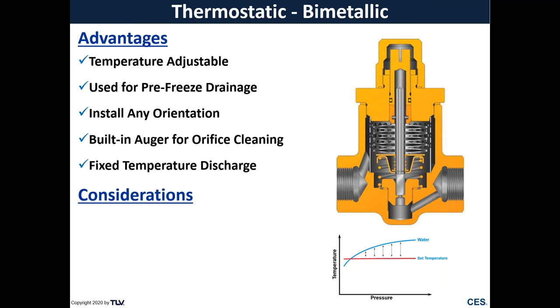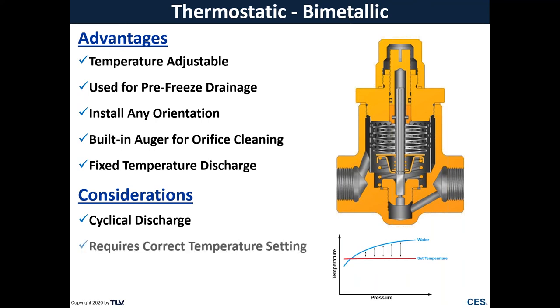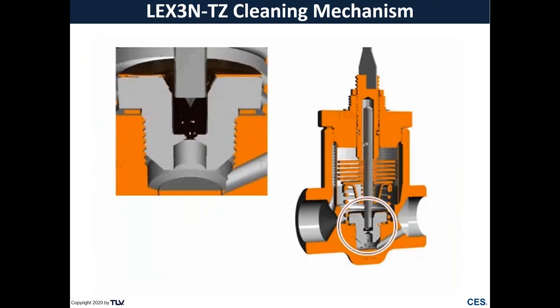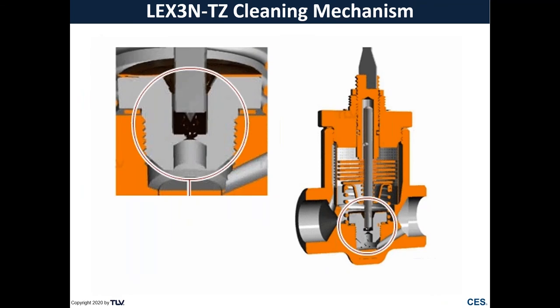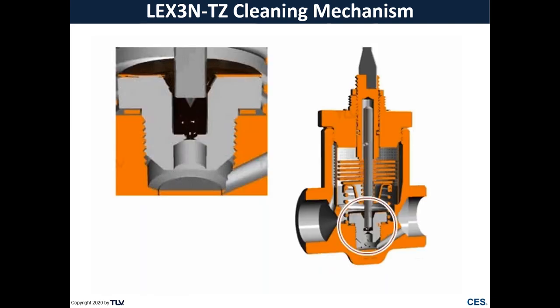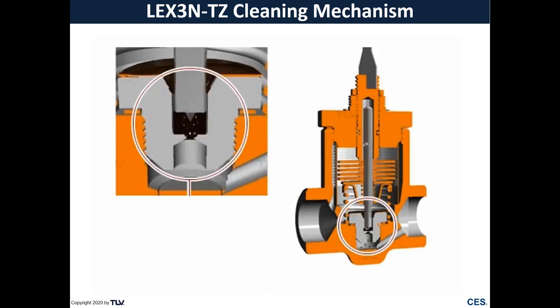Some considerations to think about when installing the steam trap: know that it is going to back up condensate just like that balance pressure element. And also you want to make sure you're setting that temperature to match your application. So let's look at the augering device. This is kind of a built-in cleaning feature that TLV has incorporated with this steam trap model. And so you can screw that adjustment screw all the way down, kind of freeing any dirt and debris that may have settled on the seating surface. This is very common in copper tracing, if you're familiar with that.